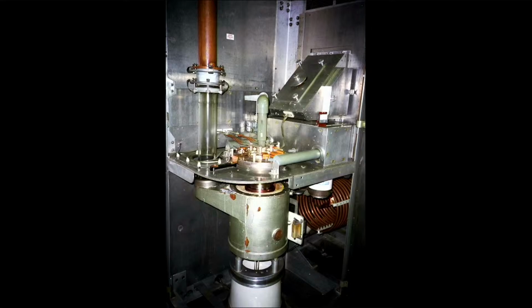And if you look on the valve jacket, you'll see a metal-clad, gold-coloured resistor. What they did was have that in line with what they want to monitor. In a little die-cast box there would be a resistor, a small resistor, and an LED. Inside that die-cast box goes the fibre optic, and I think, if my memory serves me correct, it was just glued to the LED. At the other end of the fibre optic cable, you would have the analog detector, and that was how the monitoring of the RF voltages and currents were done.